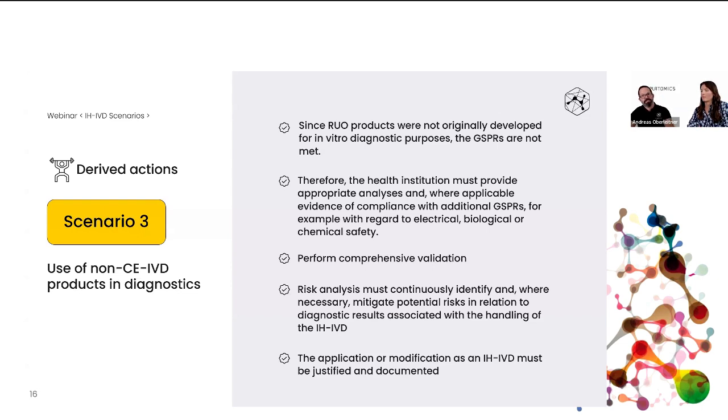For the risk analysis, you need to consider that for RUOs, potentially no one ever did a risk analysis on that product, at least not in your clinical setup or clinical context. Therefore, you need to put a lot of effort into the risk analysis of the integration of such an RUO device in relation to the diagnostic workflow. And last but not least, as always, the documentation part becomes a little bit bigger, I would say.